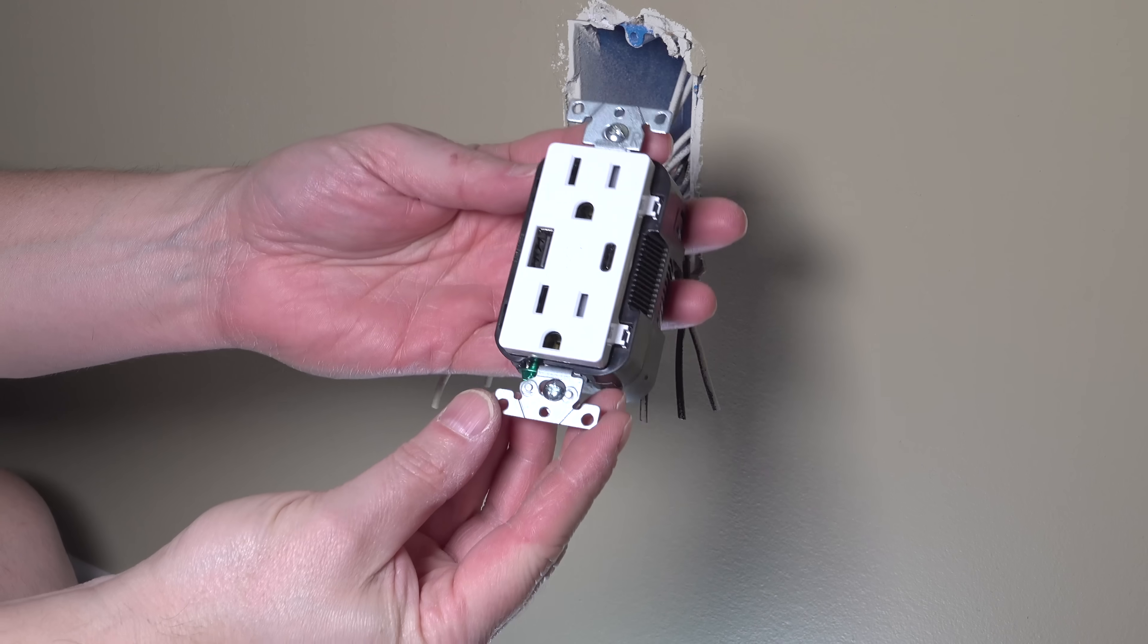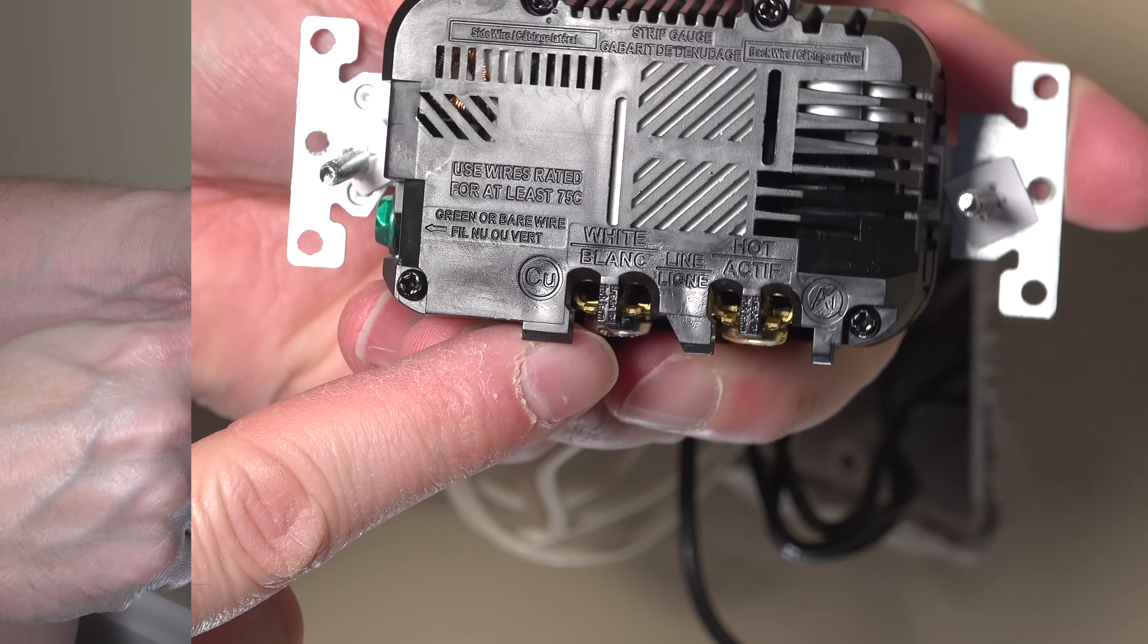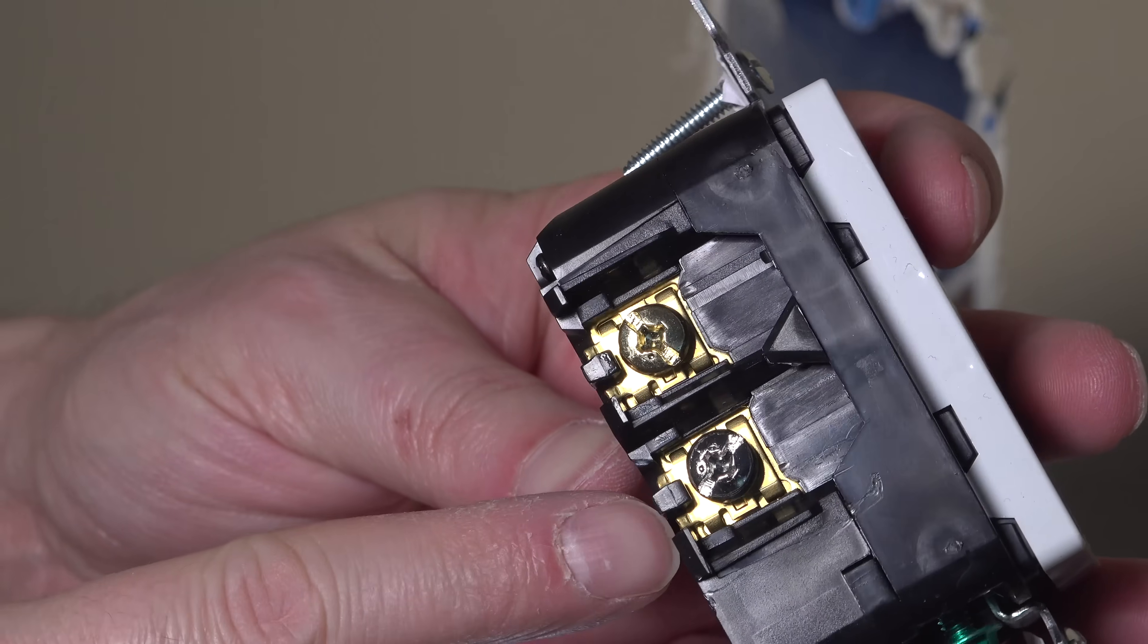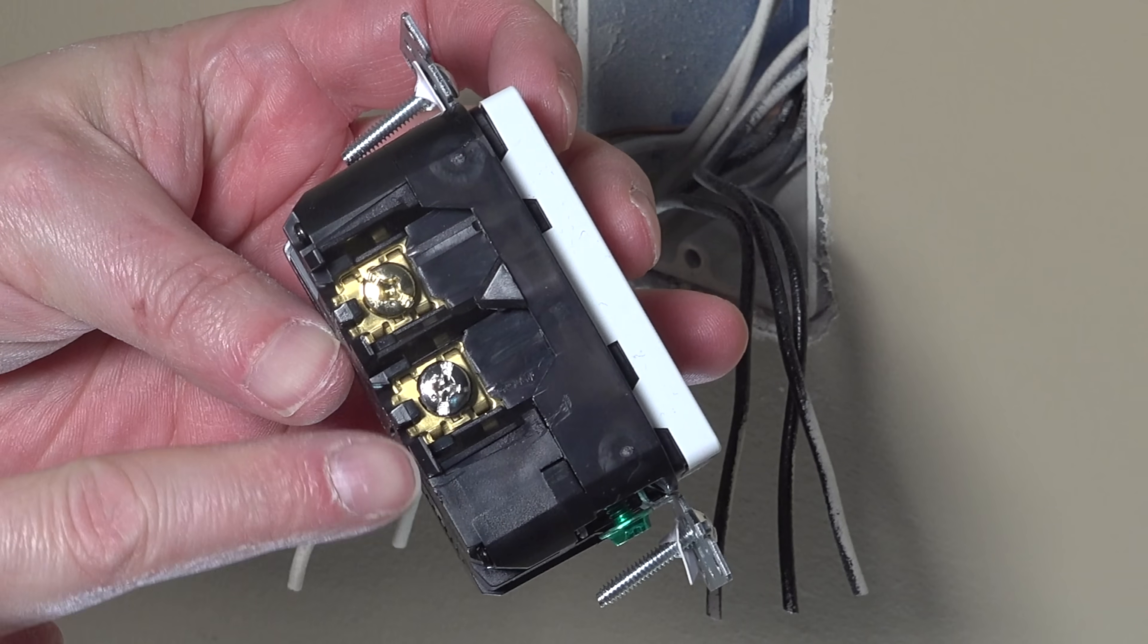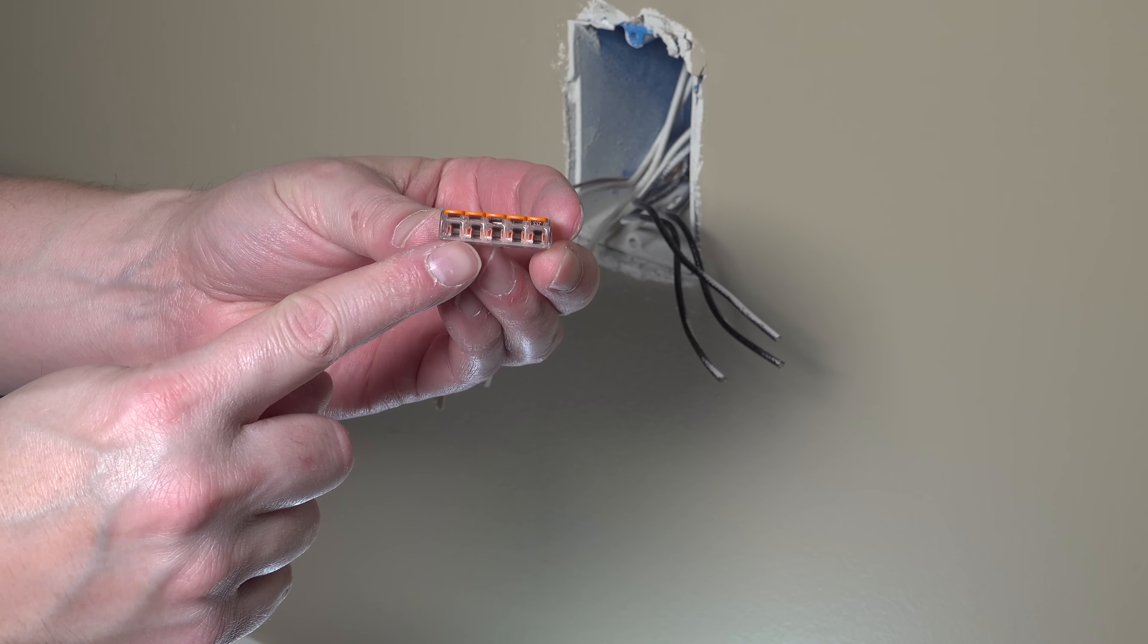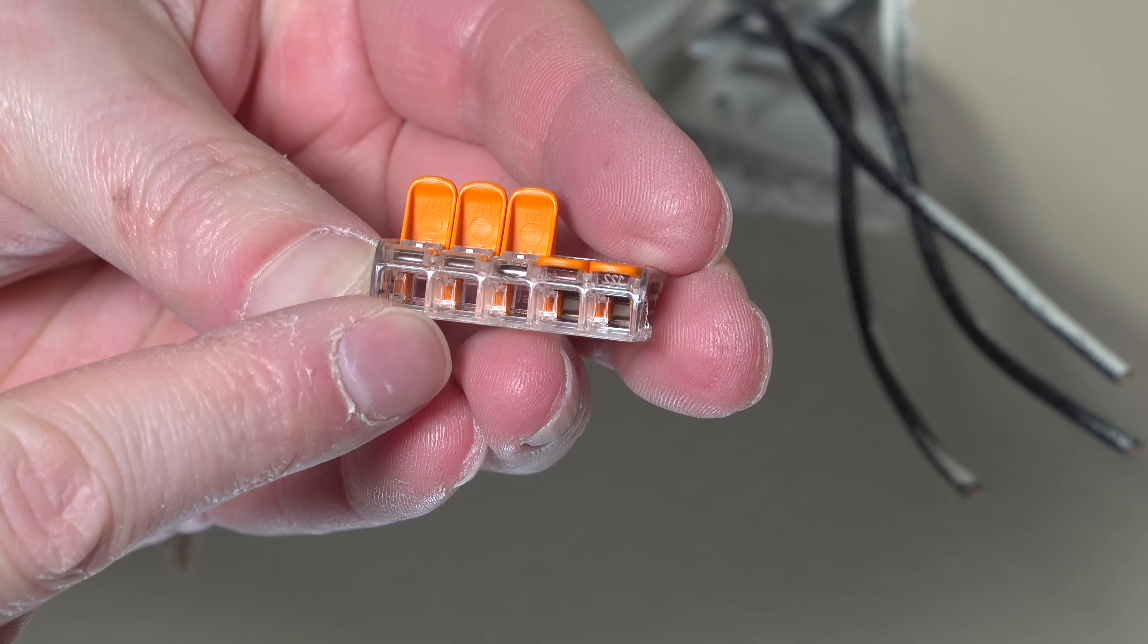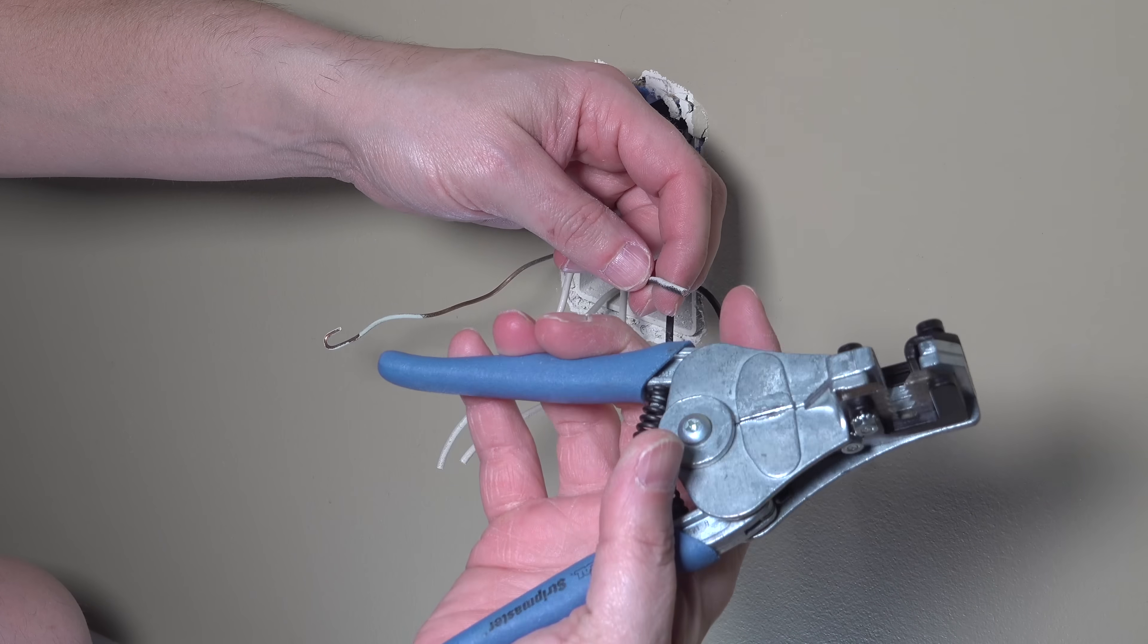Plus when we look at our new USB outlet, this only has two terminals on the side. One for hot and one for neutral. Now you can actually put two wires into each one of those terminals, but I've got three of each type of wire, so I'm going to do something called pigtailing and I'm going to use this special WAGO connector. Now you could go ahead and use a wire nut if you wanted, but this makes the job a lot simpler.